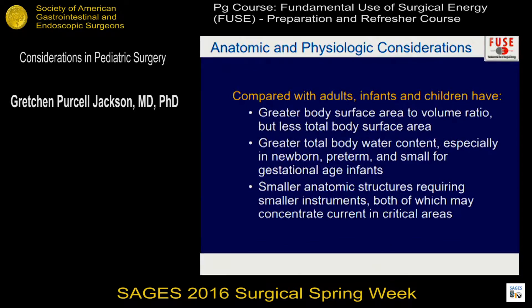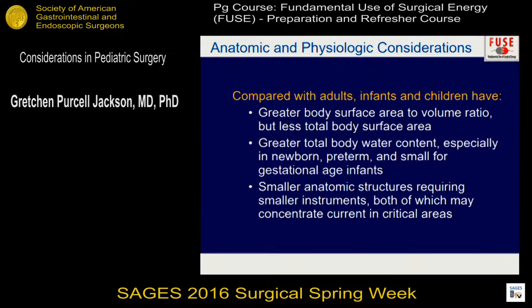Compared with adults, infants and children have a greater body surface area to volume ratio — more on the outside for what's on the inside — but they have less total body surface area. That means there is less place to put all your stuff: your monitoring devices, your dispersive electrodes, and your work area. It also means that tissues of high resistance are in close proximity to tissues with low resistance, so how your current behaves in the body will be very unpredictable. Similarly, if you operate on someone with scar tissue or implants, you need to think about those things too.